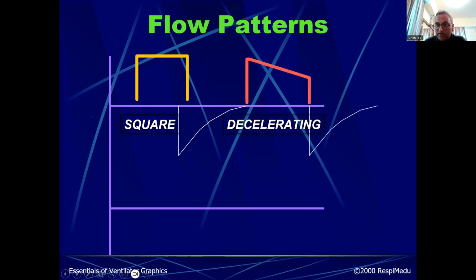There is another flow which is called decelerating flow, where the flow reaches a peak quickly and then slowly it comes down. Suppose you want to generate a pressure as a primary variable, suppose pressure ventilation, you generate the flow in such a way that a certain pressure is reached and then slowly it comes down. So this is what we use in the pressure ventilation. So ultimately it is the flow which determines whether it is a volume ventilation or a pressure ventilation. So these are the two major types of flow which are used in the modern ventilators.